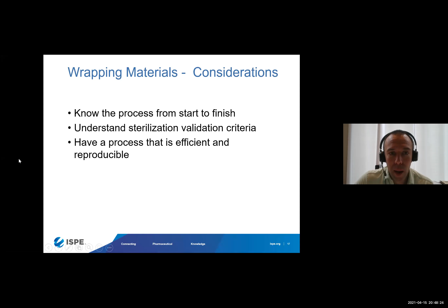So in the autoclave, certainly the way the parts are wrapped and positioned on the autoclave cart or within the equipment, this should be done such that the equipment will not hold condensation. Likewise, the wrapping material should not block condensation draining. And lastly, I mentioned this already, prepare the items in a way that will promote aseptic presentation.